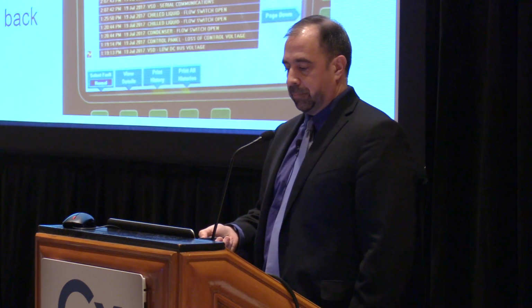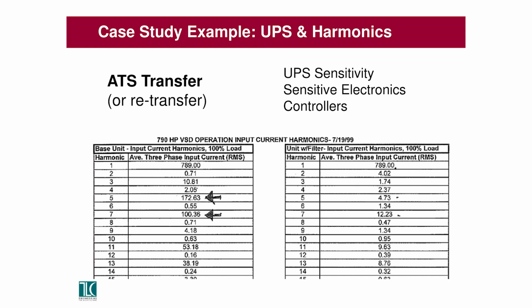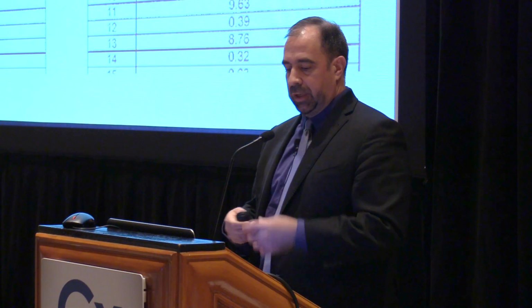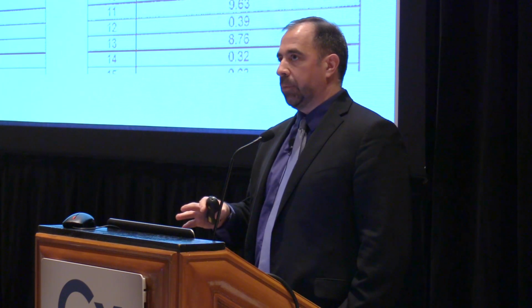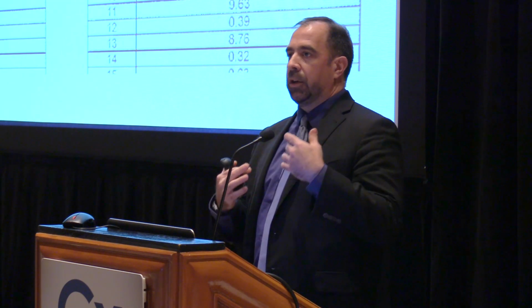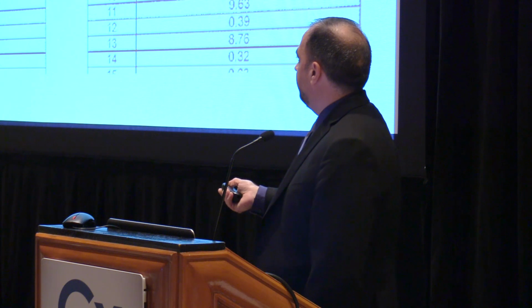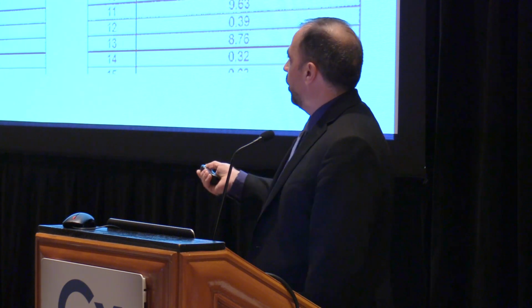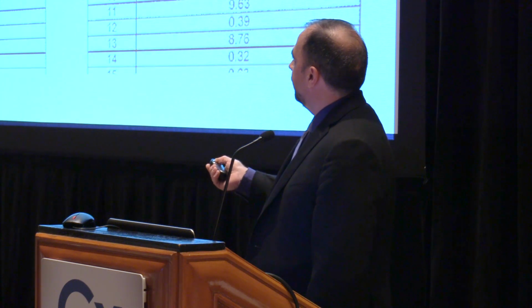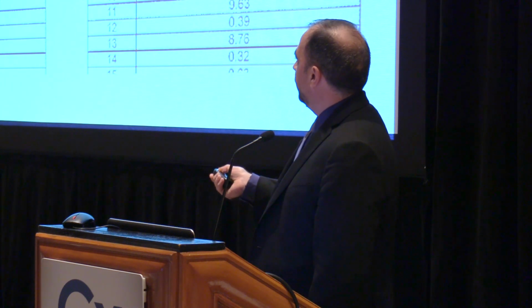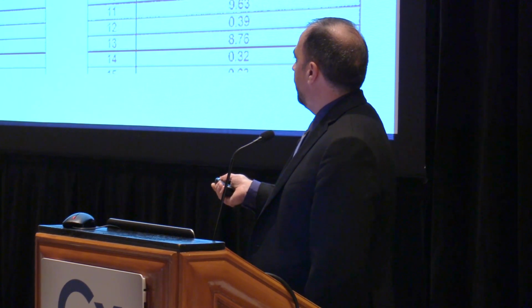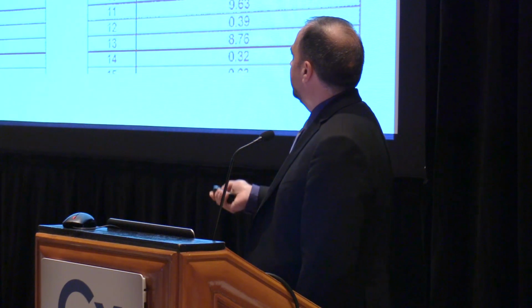The other thing that I've run into, and it's kind of weird, is harmonic issues and big VFDs producing harmonics. I've had a couple of projects where big chiller VFDs have had harmonic issues. I've seen it where it didn't have the right harmonic filtering or that wasn't addressed, but I've seen it where the VFDs did have some harmonic filtering too. This chart is supposed to show, on one project in particular that I'm thinking of, the harmonic values without filtering and with it, and you can see the 5th and 7th harmonics have some big numbers there. So this is what we had.